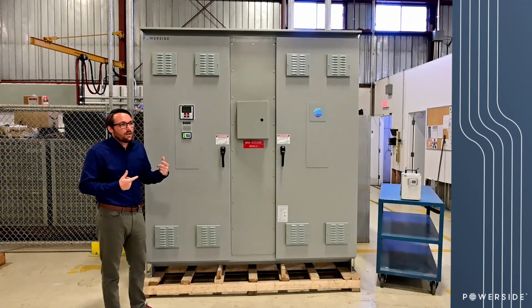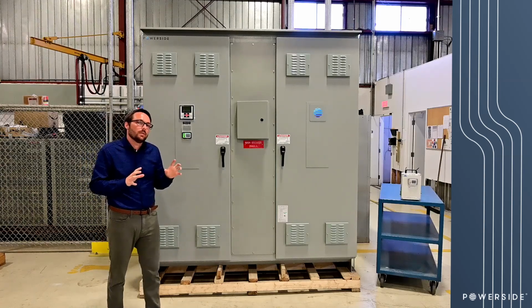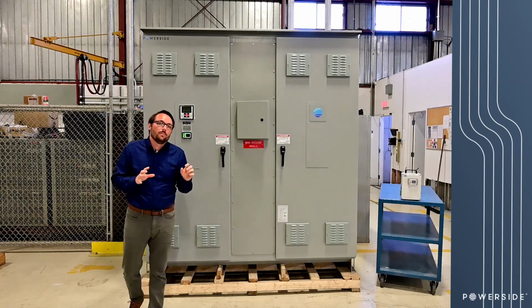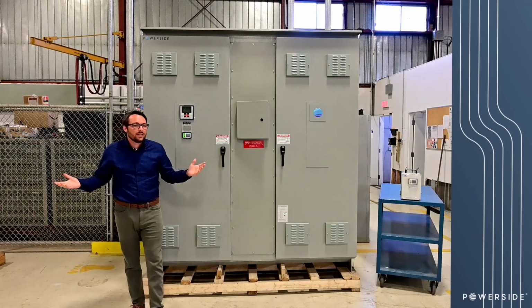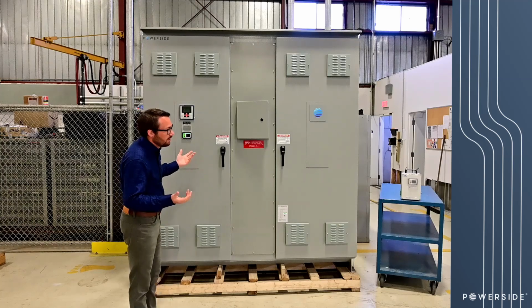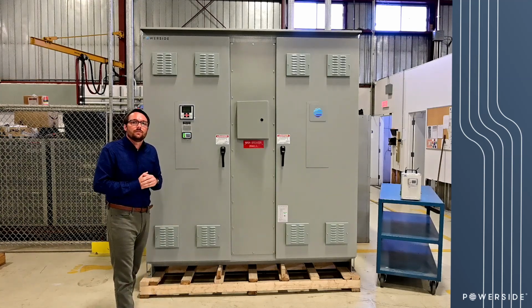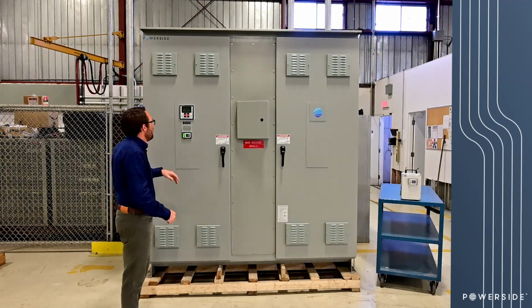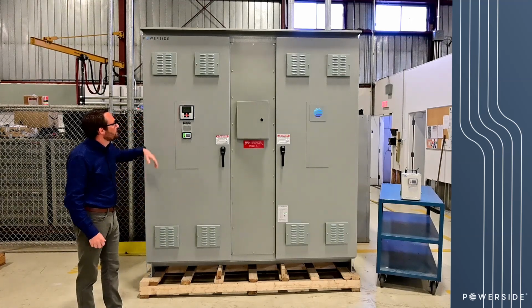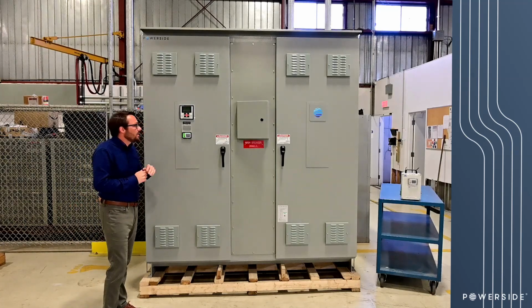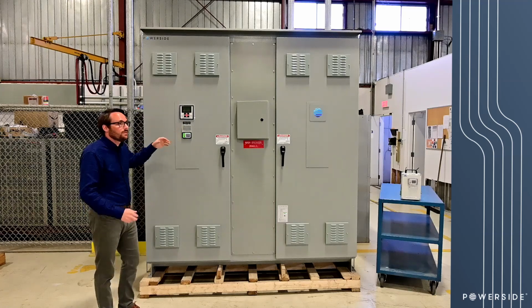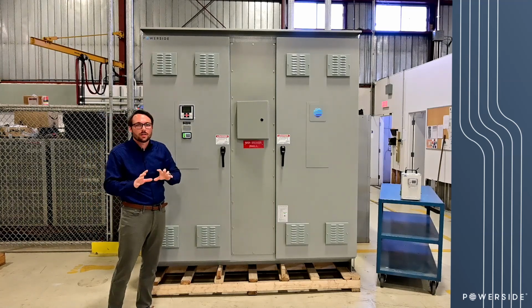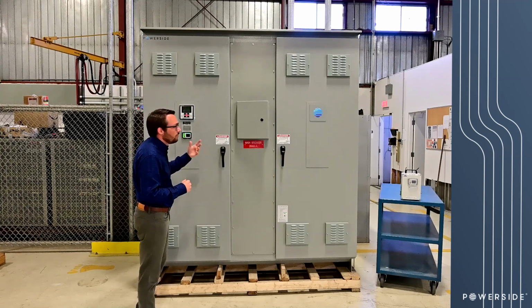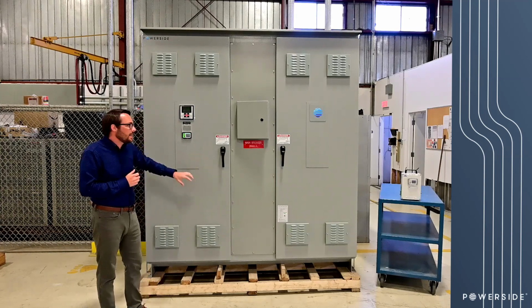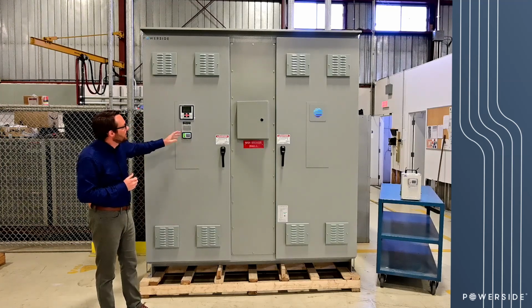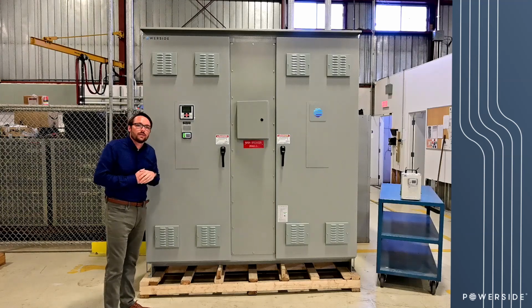And I mentioned earlier about the fact that this client had several capacitor banks that previously failed at their site. They had no idea that they failed. They had no idea when they failed. It just kind of was a slow death of all of the power factor correction that they had in that facility. Well, what we did here is we're using our power factor control relay, and we've set up different alarm conditions. So if there's an event where there's undercompensation or overcompensation or a blown fuse or something that occurs inside this system, we've actually wired this digital input through the alarm contact on our power factor controller.